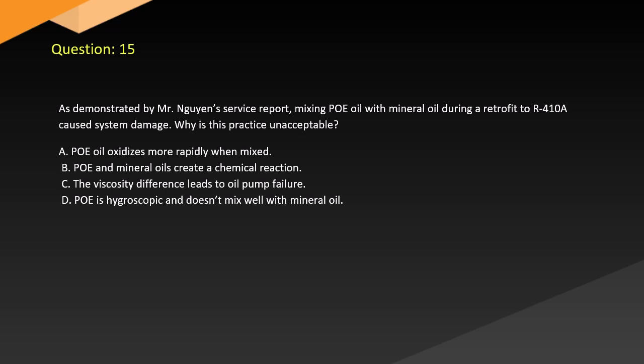A. Oil oxidizes more rapidly when mixed. B. POE and mineral oils create a chemical reaction. C. The viscosity difference leads to oil pump failure. D. POE is hygroscopic and doesn't mix well with mineral oil.